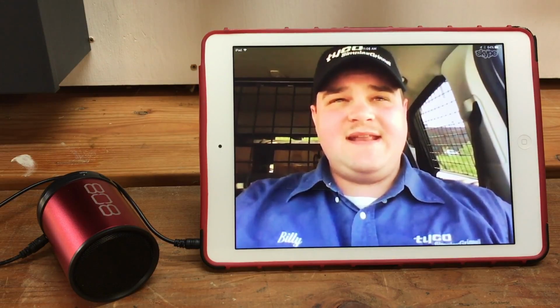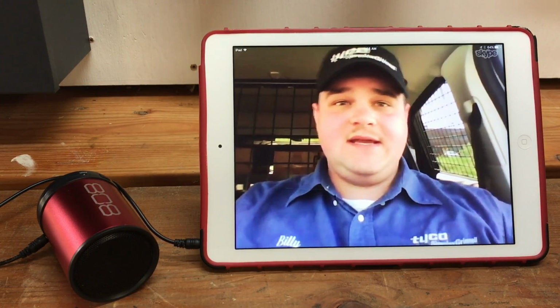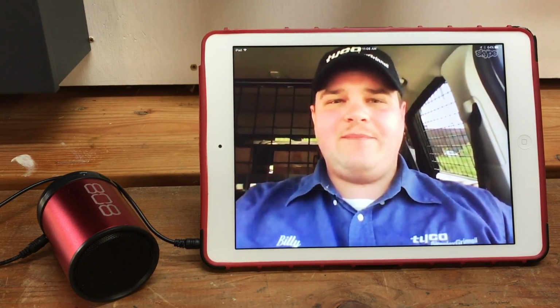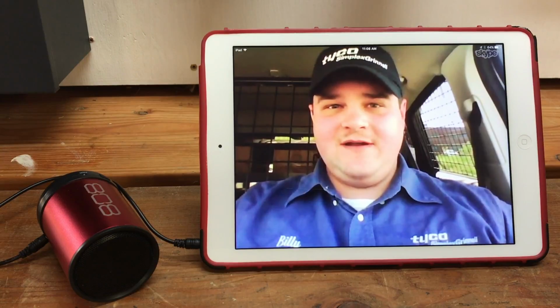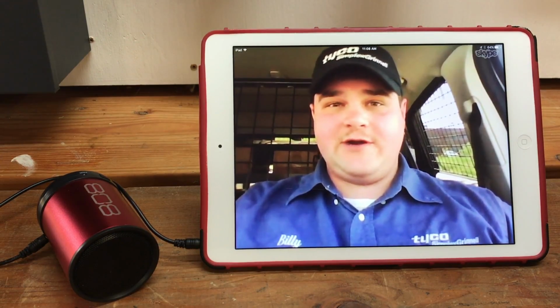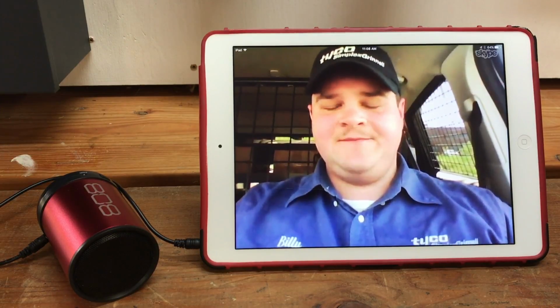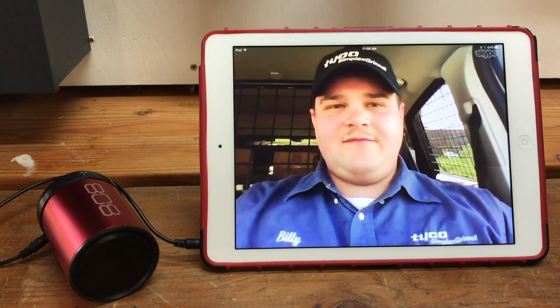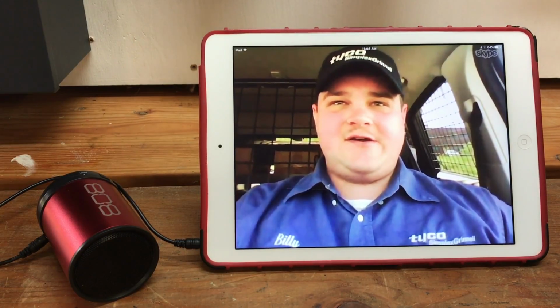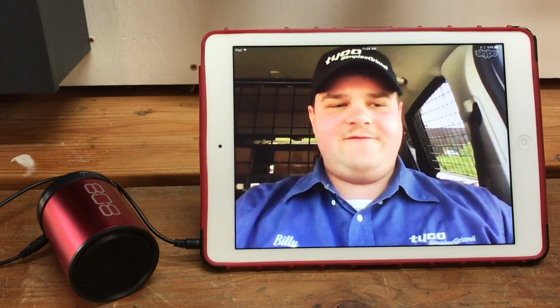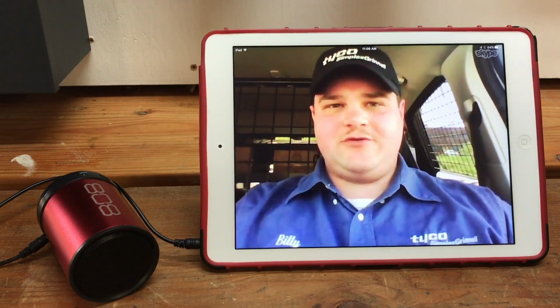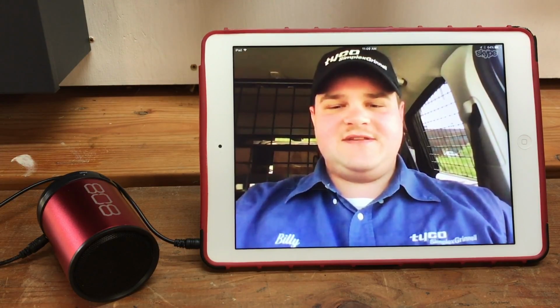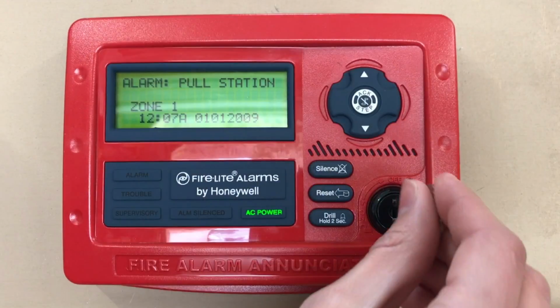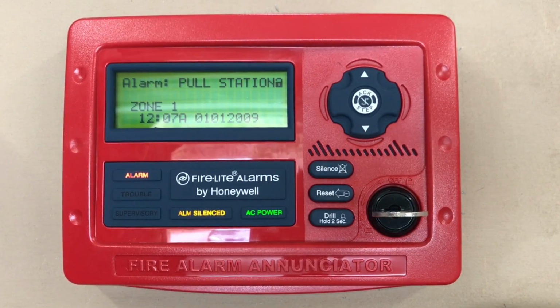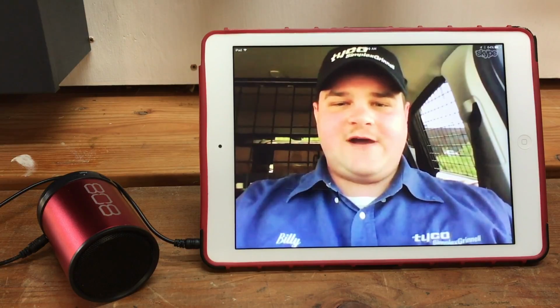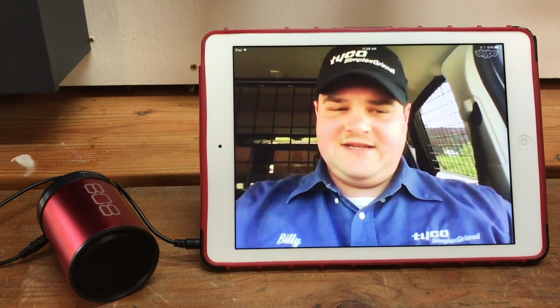The most not-up-to-code thing I frequently see is places that pile up objects in front of the fire alarm panel, not allowing at least 3 feet of clearance around it for access. I've seen tables and chairs stacked in front of the panel in a mechanical room or storage room. These places pile stuff up because they figure that since they have an annunciator, they don't really need to get to the panel itself. That's not the case for fire alarm technicians and inspectors like me who need to get to the system to work on it.